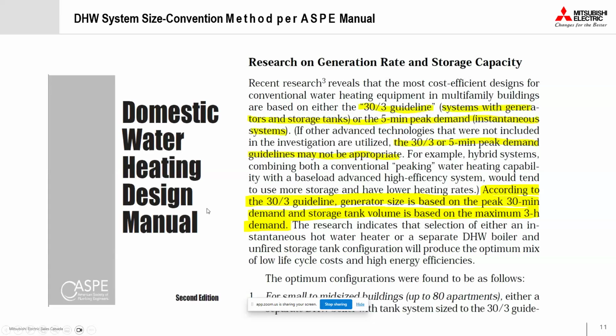In terms of design guides, there are a few resources available. One of them is the American Society of Plumbing Engineers. Generally, they use either 30/3 or 5-minute peak demand terminology. According to the 30/3 guideline, the equipment is based on the building's peak 30-minute demand, and your storage volume is based on the 3-hour maximum demand. Your equipment should be sized so that it can meet the 30-minute demand, and your storage together supplies the hot water for both the 30-minute and 3-hour demand.